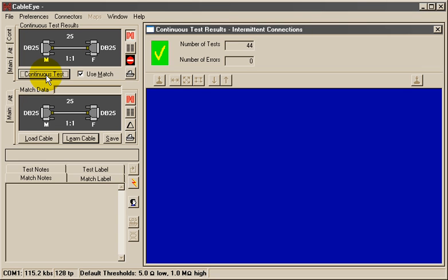If you suspect a particular conductor of having an intermittent connection, you may highlight that conductor in the schematic, and, if you're using an M3 tester, continuously measure the resistance of that particular conductor as you flex the cable.